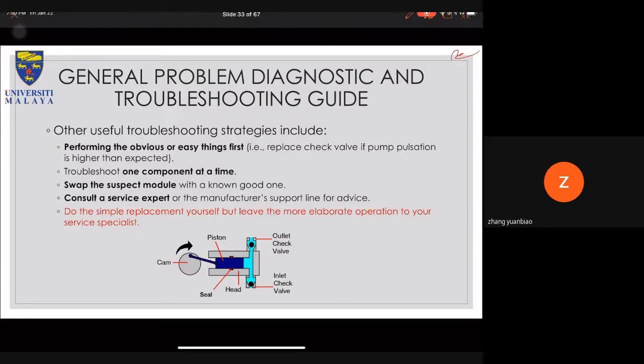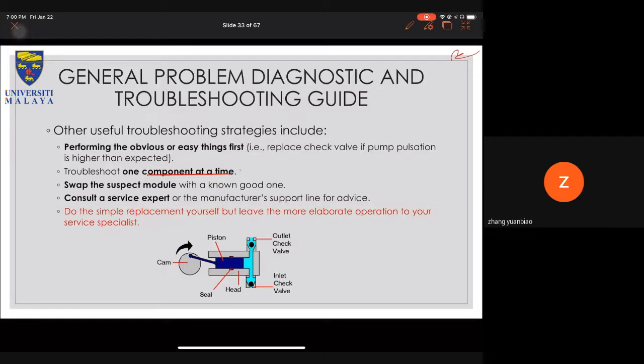So normally you want to run one component at a time, and to do this, you normally start from the detector and go backwards until you reach your solvent reservoir. Unless it's a leak that you can identify straight away, then of course you don't need to check each module. But in case there's an air bubble, you know that your system has a degasser. Your HPLC system is normally equipped with a degasser, so there shouldn't be any bubbling issue, but then your detector says otherwise, and by running the pump at a higher speed, you can remove the bubble.